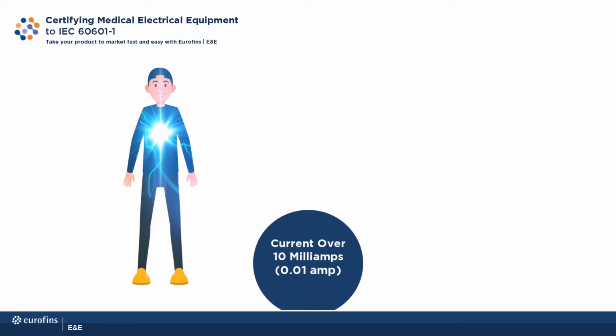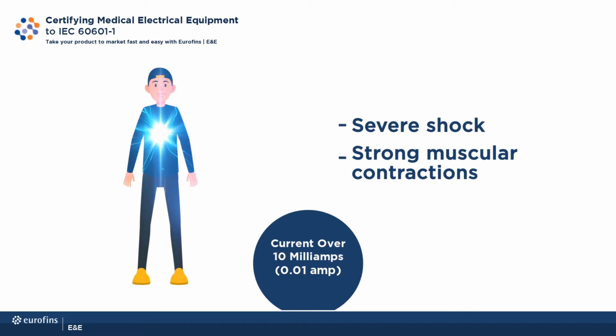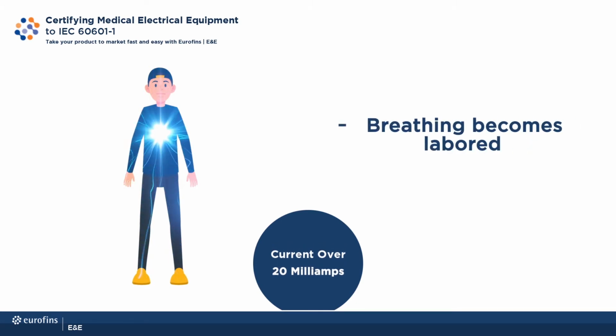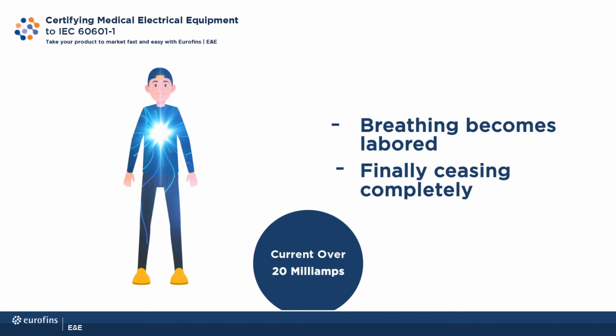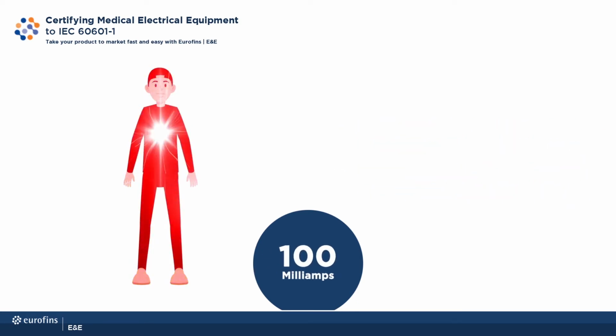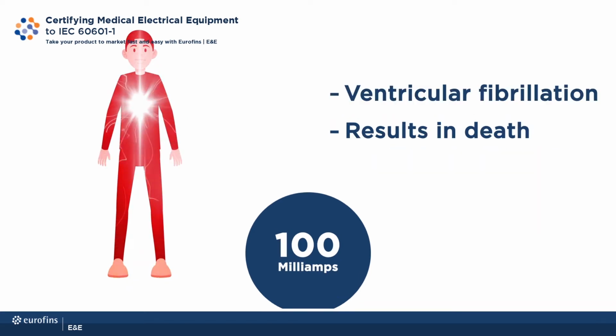Let's look at that for a moment. Any amount of current over 10 milliamps, or 1/100 of an amp, can produce painful to severe shock with muscular contractions that are so strong the victim cannot let go of the wire that is shocking them. At values as low as 20 milliamps, breathing becomes labored, finally ceasing completely, even at values below 75 milliamps. As the current approaches 100 milliamps, ventricular fibrillation of the heart occurs, an uncoordinated twitching of the walls of the heart's ventricles, which results in death. Without proper isolation from the high leakage current, a person can die, and the patient with open skin, who may be unconscious or bedridden, is more susceptible, can't call for help, and can't move away from equipment with high leakage current.